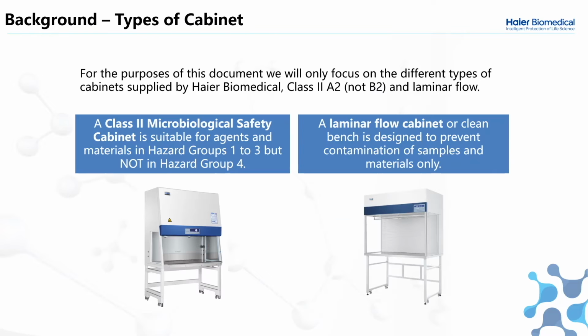Haier Biomedical offer two different types of cabinet in our clean air range, which is our class 2 microbiological safety cabinet. This is appropriate for hazard groups 1 to 3, but not for group 4. And our laminar flow series, which is appropriate for hazard group 1 exclusively. These both have different functions and different use cases, and going forward I'll go through each use case and where each is appropriate.